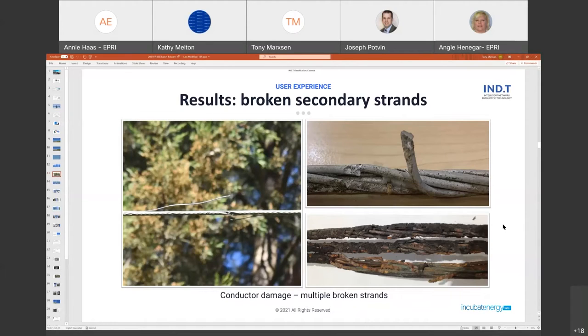That's a three-core customer service line. It's called by the line crews 'licorice strap', because it's a flat rubber strap that's got three cores running through it. You can see how internal discharge is progressively eating away the insulation until there's been quite a serious failure. This one we alerted the utility to about 3.5 days before it actually failed. In fact, it failed while the crew were on their way to investigate it.